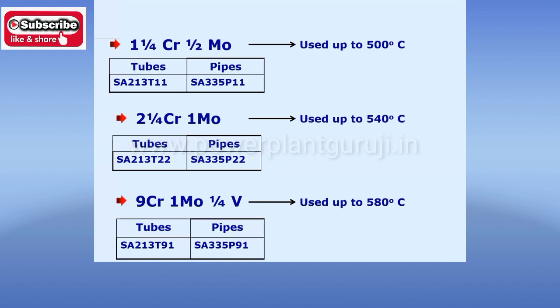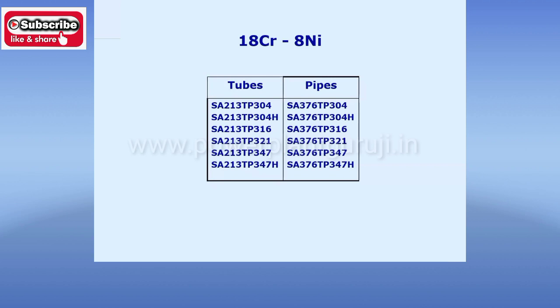Beyond T91, if we add more alloying elements, we have high alloy steel — the austenitic stainless steels. In a 500 MW or 660 MW unit, the final few coils of the final superheater and the hot reheater will be made of austenitic stainless steel. The austenitic stainless steel used is called 18-8, meaning chrome is around 18% or a little more and nickel is around 8% or a little more. In boiler metallurgy, the alloys used in the final superheater and final reheater are SA213 TP304H and SA213 TP347H.